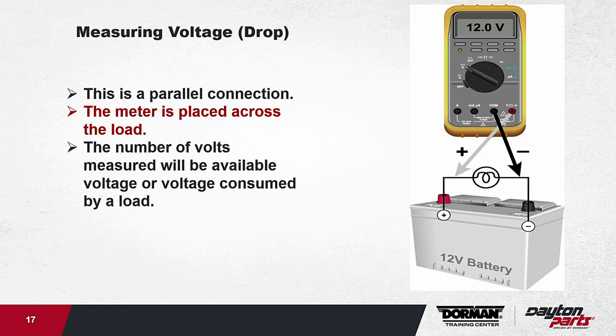Meter is placed across the load, and the number of volts measured will be the available voltage, or voltage consumed. The key is to look at it as voltage consumed by a load. And that's a good way of starting a voltage drop test.